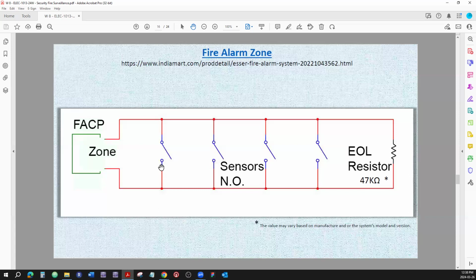Now that's another condition - what if there's an actual fire and one of the sensors detects it? Normally those fire sensors are in the open position, as opposed to security alarms which have to be closed because everything is in series. For fire alarms, everything is in parallel, so those devices are normally open sensors. If there's a fire, let's say this is a smoke detector, it detects smoke and closes. So now the zone sees 0 ohms, a closure - boom, fire alarm, all kinds of things trigger: annunciating, bells ringing, and all that. So that's how fire alarms work.